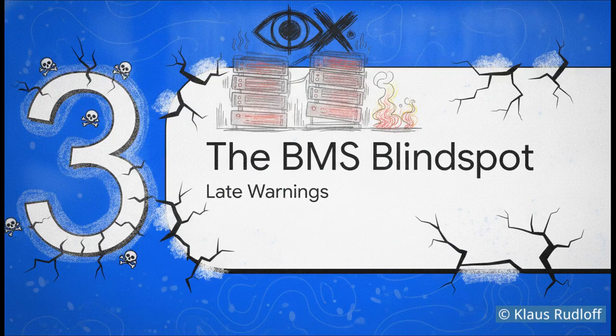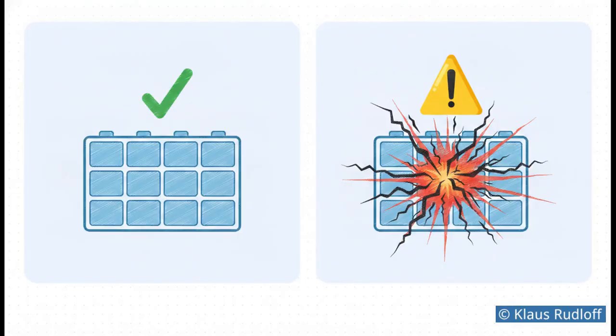All right, Section 3, the BMS sensor blind spot. If this degradation is happening deep inside the racks, why are we only getting late warnings? This highlights the core problem perfectly: there's a massive gap between theory and reality. Datasheet thermal averages promise us a perfect, flawless world, but the actual field reality is completely riddled with micro-hotspots. Relying on those datasheet averages completely masks what is actually happening in the trenches. An average temperature across the board might look perfectly safe, even while the dead center of your rack is physically degrading from all that excess heat.